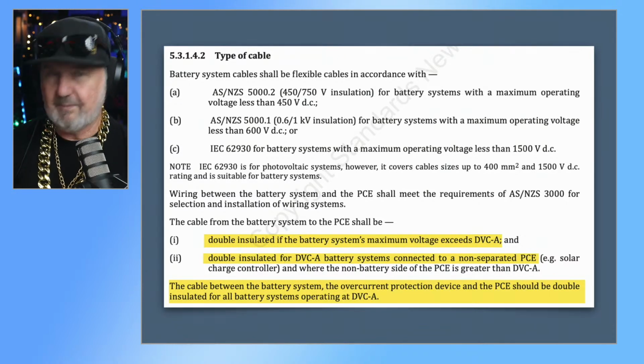And I know certainly in New Zealand, there's been quite a bit of discussion about this, which is how do you know if an inverter that's connected to a DVC-A battery, which is therefore a 60 volt battery or less, connected to a multi-mode inverter, such as a hybrid inverter or an off-grid inverter, whether that inverter is galvanically isolated. Because if it's not, you can't use it. That's the wording in 4509 Part 1, the standard for standalone power systems. It's also in 4777 Part 1, which is you must have galvanic isolation for DVC-A battery systems connected to PCE. So if it's not, then you can't use it because you've got a hazardous potential at the battery terminals.